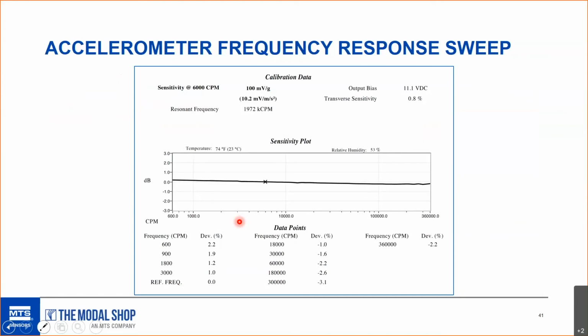And yeah, on a precision accelerometer that you're using with a portable vibration analyzer, you're going to rely on this accelerometer to take thousands of data points. You're going to use it every day, on a variety of pieces of machinery. You might walk up to an electric motor or a pump or what have you. And it's important that the accelerometer is tested throughout the frequency range so that you don't have any areas of localized resonance. A sensor that is producing an elevated signal at high frequency can produce a false alarm, which is almost as bad as a real alarm.